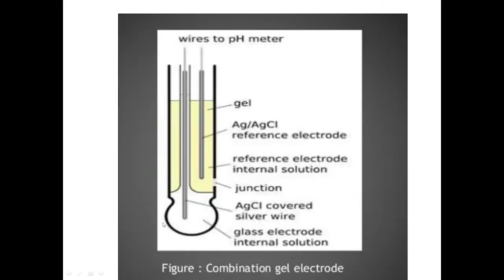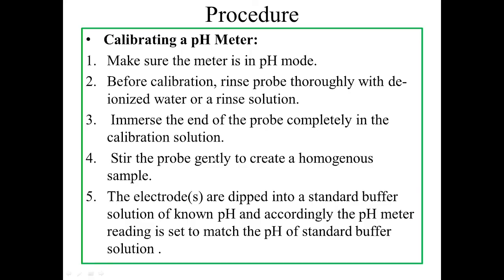So this is the bulb of the probe. You have to completely immerse it in the calibration solution. After immersing the bulb, you gently stir the probe so that a homogeneous sample is created. Now, the electrode is first dipped into a standard buffer.